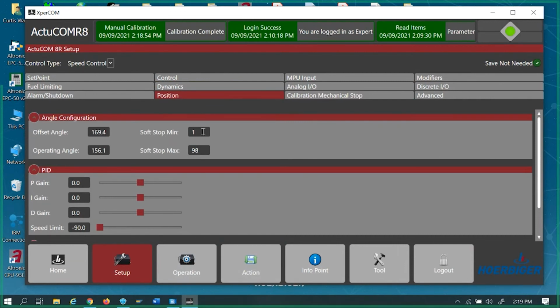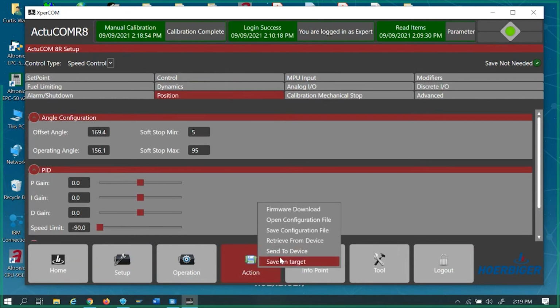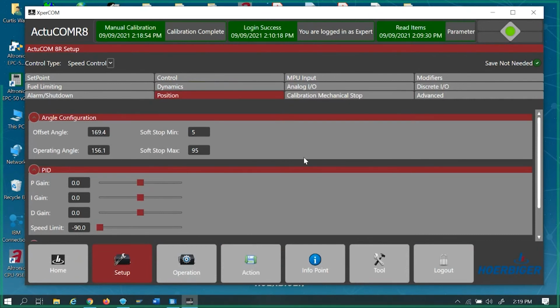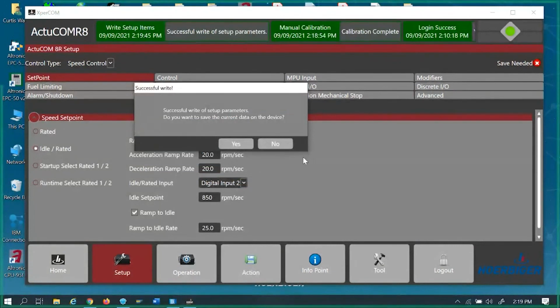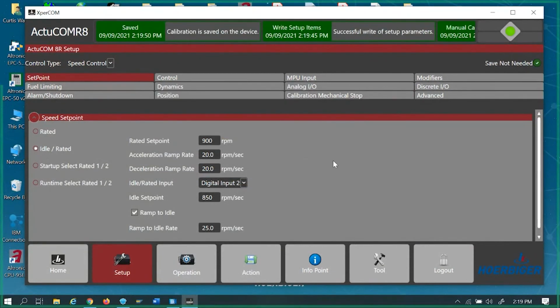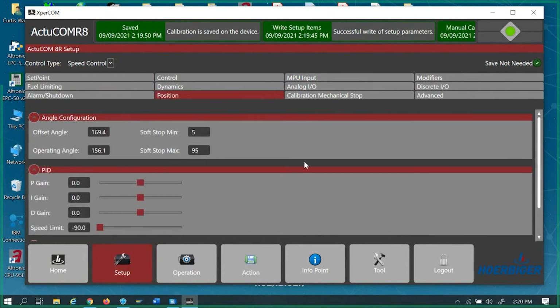Right here on the soft stop minimum, soft stop max, you can actually keep it from hitting it. The default on these is usually like 5 and I think it's 98 or 95. So what that does, it will stop at 5% before you get to that bottom where you calibrated it. I've used that also. If I don't have enough fuel, I can ease it open a little bit more, 2 or 3 more percent. Sometimes it would be fine, but typically that's not the correct way to do it.